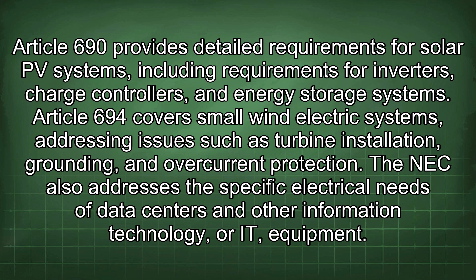The NEC also addresses the specific electrical needs of data centers and other information technology, or IT, equipment. These requirements address issues such as grounding, bonding, and power quality. Article 645 provides requirements for information technology equipment rooms, including requirements for disconnecting means, overcurrent protection, and grounding. It also addresses issues such as power quality and the need for uninterruptible power supplies, or UPS, to protect sensitive IT equipment from power outages.